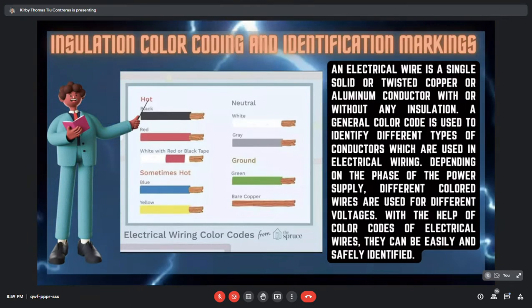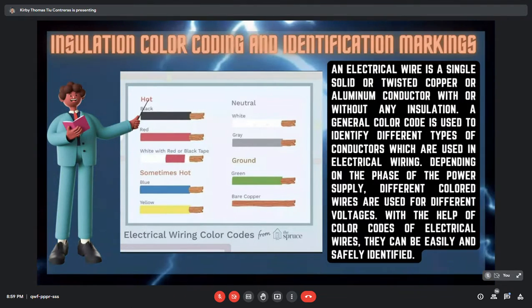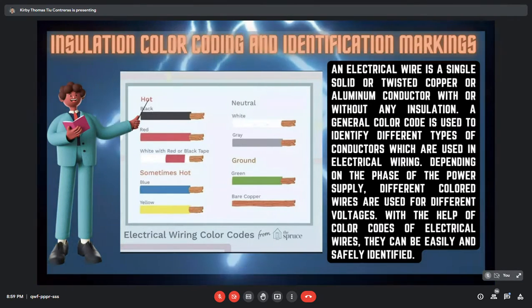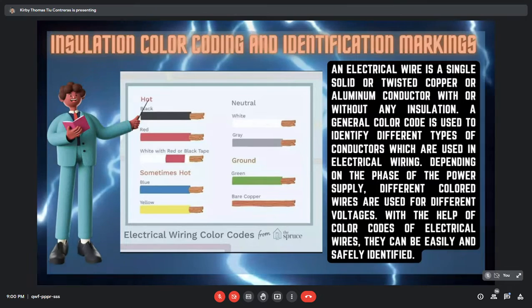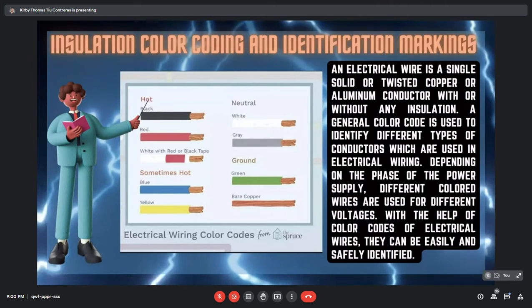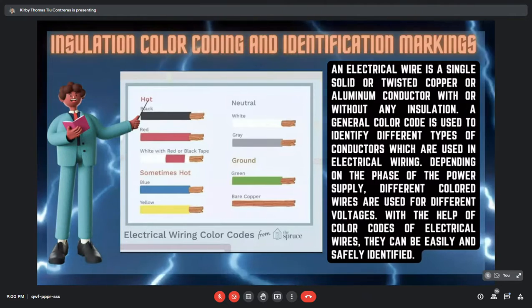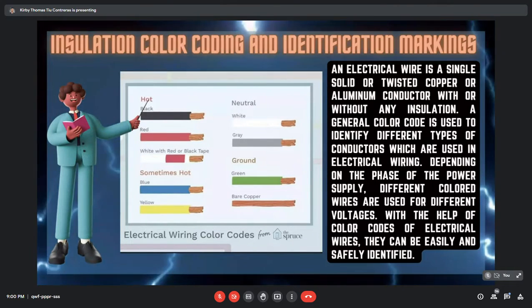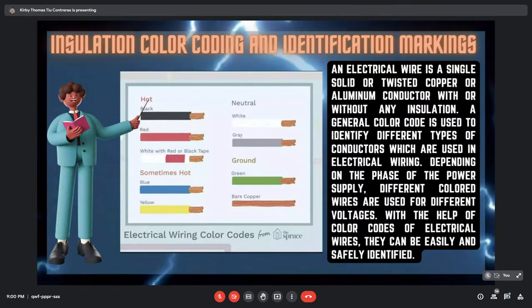In the picture, the black wire is always used for hot wires, and it is common on standard household circuits. Red is also designated as a hot wire, and white with red or black tape is also a hot wire, while white and gray are indicated as neutral wires. Green and bare copper, or green with yellow stripes, are for grounding, and blue and yellow is sometimes indicated as hot. So next.